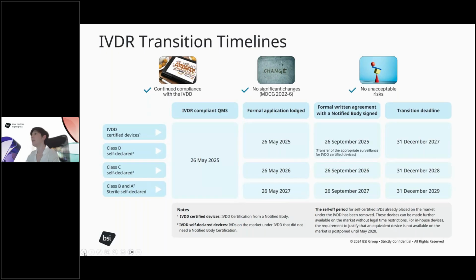If all these conditions, together with the previous ones I mentioned, are fulfilled, then the transition deadline is pushed back to December 2027. For Class C devices, the formal application should be lodged by the 26th of May 2026 and the written agreement should be signed by the 26th of September 2026. This, together with the other conditions, will allow the transition period to end in December 2028. And for Class B and A sterile devices, the application should be lodged by the 26th of May 2027. The written agreement should be signed by September 2027. This way, the transition period is pushed back to December 2029.